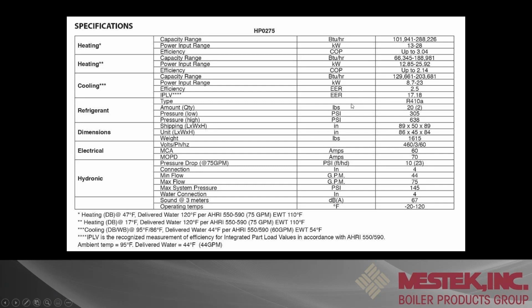So if I'm looking at amp draw, our amp draw is about 60 amps, and then our MOPD would have to be a 70 amp breaker on that. And as far as voltage goes, there's only one voltage option on this product, so it's 460 volt, 3-phase, 60 hertz.